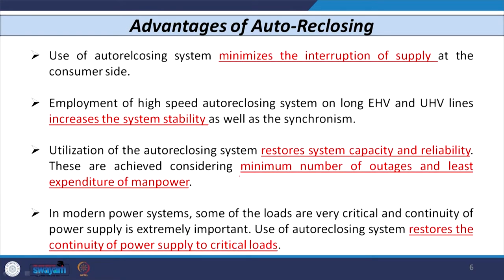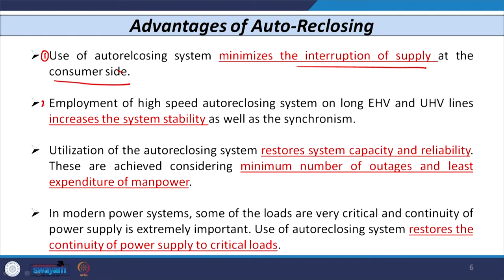The first advantage of auto reclosing is that it minimizes the interruption of supply at the consumer side. Whenever a reclosing attempt is made and the faults are transient — as 80 to 90 percent of faults on overhead conductors are — these faults may die out after the first reclosing attempt and the electric supply continues, minimizing interruption from the customer viewpoint. The second advantage is that high-speed auto reclosing for EHV and UHV lines improves system stability and synchronization.